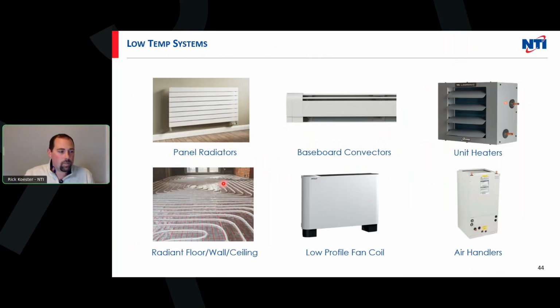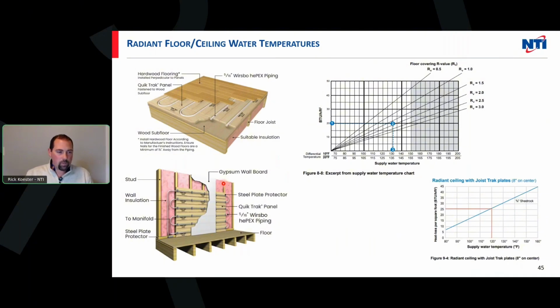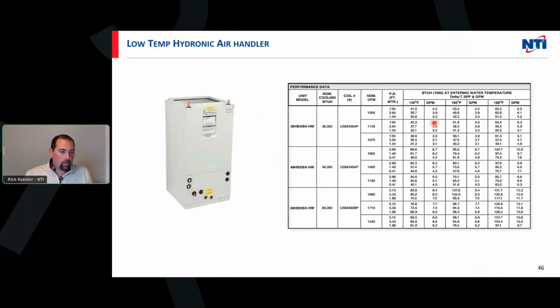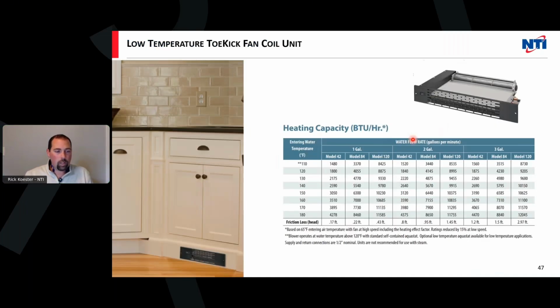You look at all of these different types of systems that are out there today, from panel rads, baseboard convectors, air handlers, unit heaters. We've seen a lot of these out there in the field. I just pulled some stuff that I was familiar with. Radiant floor systems, they're talking about supply water temps anywhere from basically 70 degrees all the way up to 130, really up to about 150 is the max. Anything over that, we're worried about damaging floors. So that's radiant, and the guys are pretty comfortable doing that, but they're not used to putting 140 degrees through an air handler, right? We're getting BTUs, and that's what we need to teach them, is understanding how to deliver BTUs, not the water temp. If I look at a toe kick heater, we've seen these before. They're showing water temps down to 110 degrees.